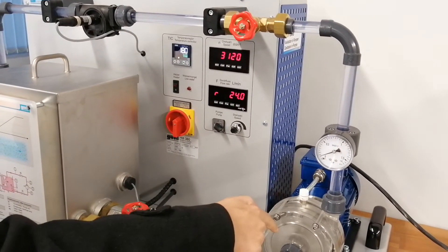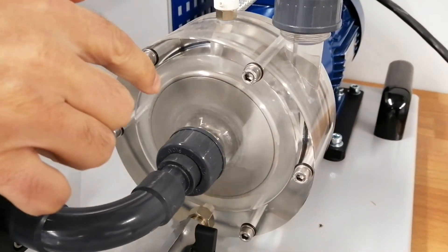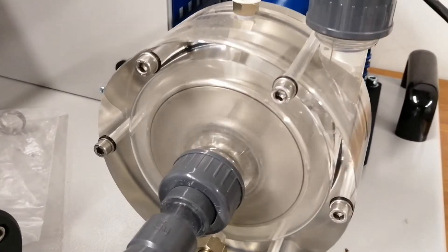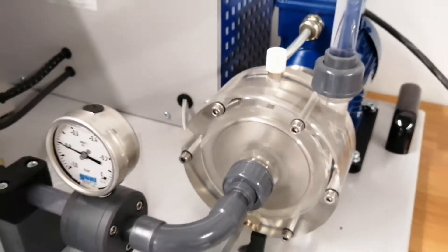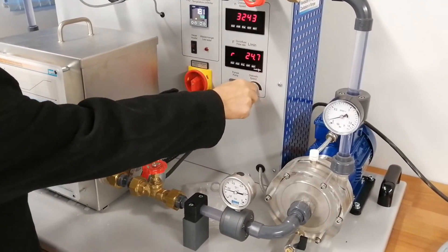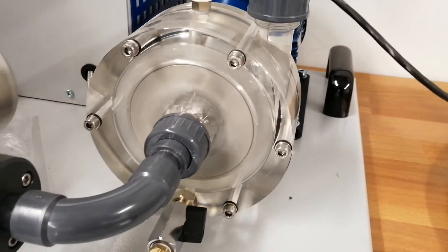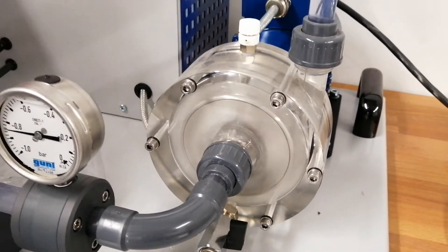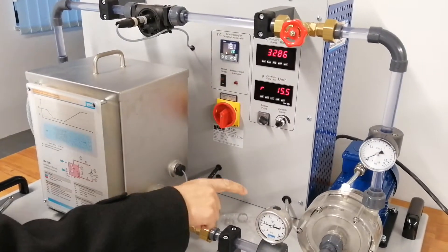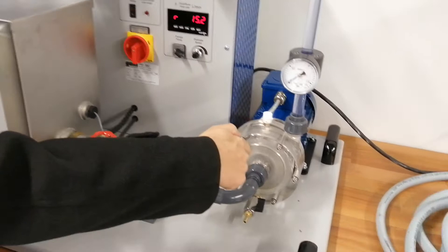Now you can observe some cavitation there. Can you see bubbles? Some bubbles and some sound. Can you hear that? Now you can observe better. Because cavitation is higher now. You see, cavitation is higher. And bubbles, you can see those bubbles.